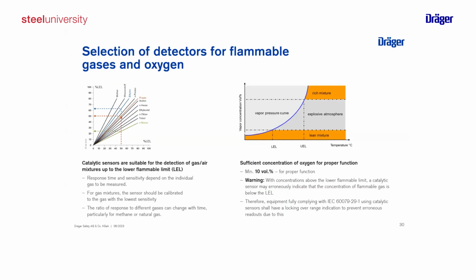Okay, so as mentioned, we always have the oxidation process with our gases, and mostly it's hydrocarbons, but we can also detect hydrogen with this. Depending on the molecule structure, we get different signals, which are related to the thermal reaction. When you use sensors like this, the best and safest way is always to calibrate, to adjust the sensor to the substance with the lowest sensitivity you are expecting, to always have the correct signal on your side.